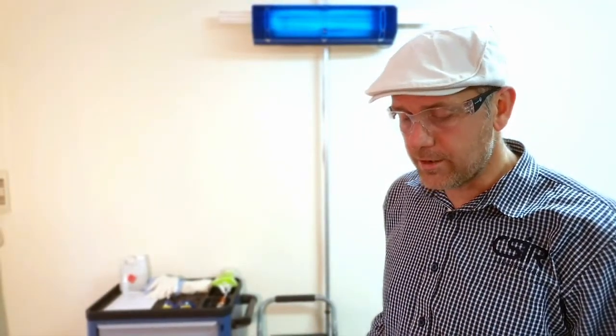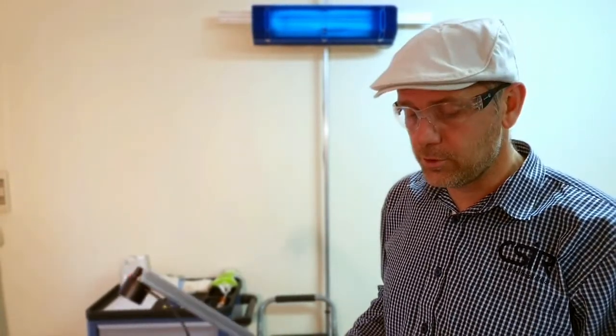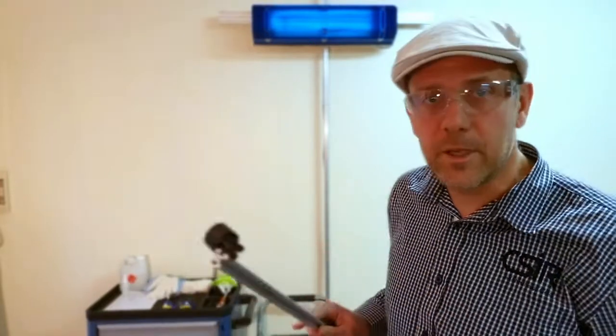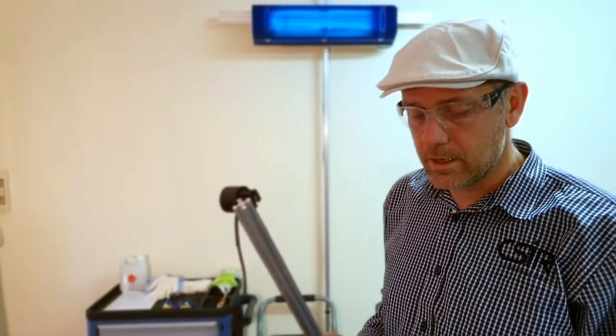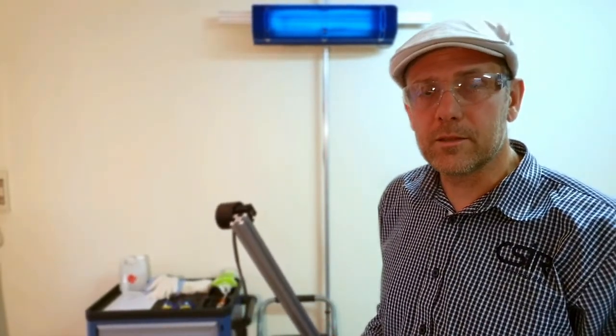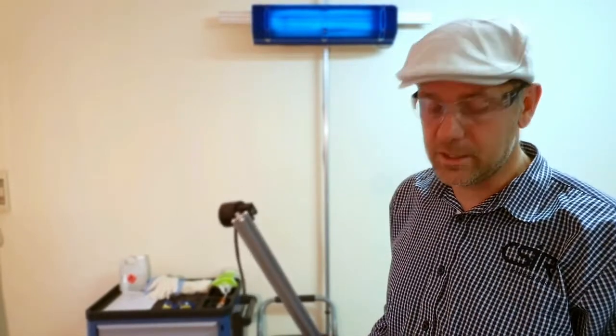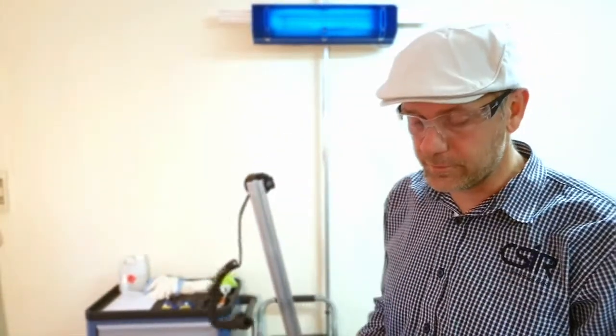So before we get up on a ladder to do any maintenance and part replacement inside the device, we need to take some reference measurements with our radiometer. We have zeroed our radiometer and switched off all the other devices in the room. You might even want to switch off fluorescent lighting in the room because this can also interfere with your measurements if you don't trust the filter in the sensor of your radiometer. And then we will start with a 1.7 meter eye safety measurement, 1.7 meters above floor level.